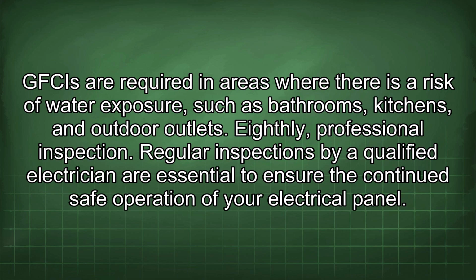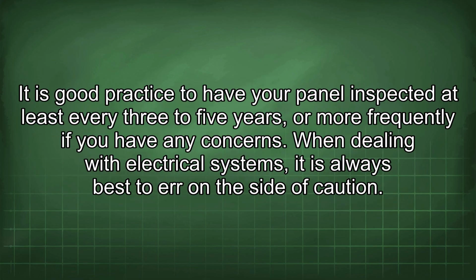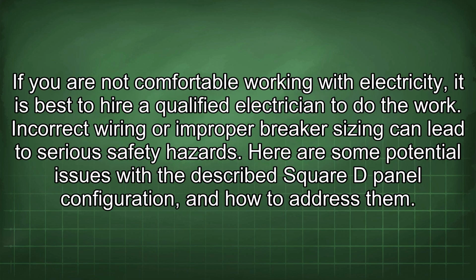Eighthly, professional inspection. Regular inspections by a qualified electrician are essential to ensure the continued safe operation of your electrical panel. It is good practice to have your panel inspected at least every 3 to 5 years, or more frequently if you have any concerns. When dealing with electrical systems, it is always best to err on the side of caution. If you are not comfortable working with electricity, it is best to hire a qualified electrician to do the work. Incorrect wiring or improper breaker sizing can lead to serious safety hazards. Here are some potential issues with the described Square D panel configuration and how to address them.